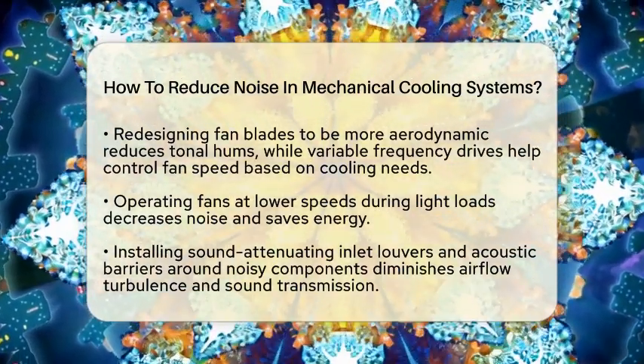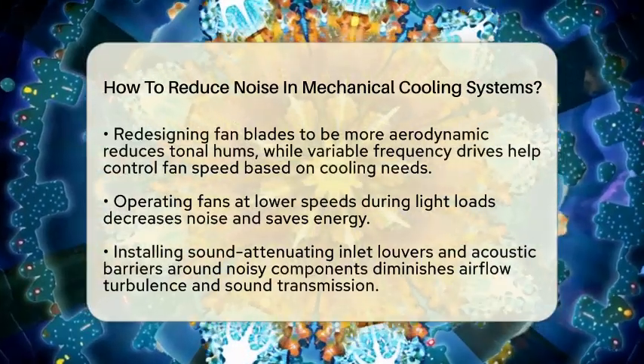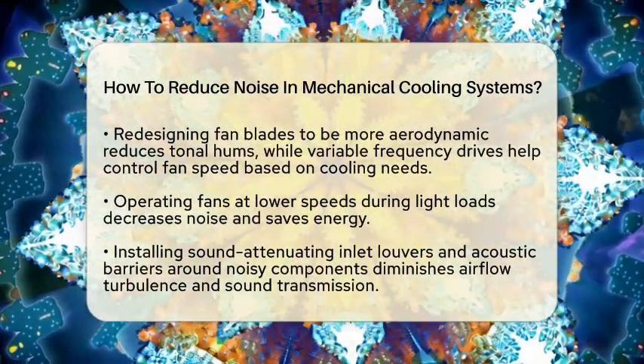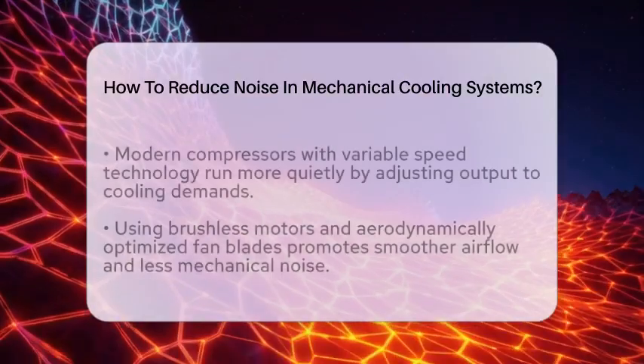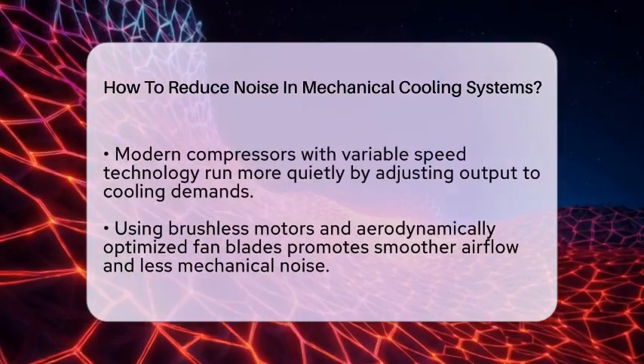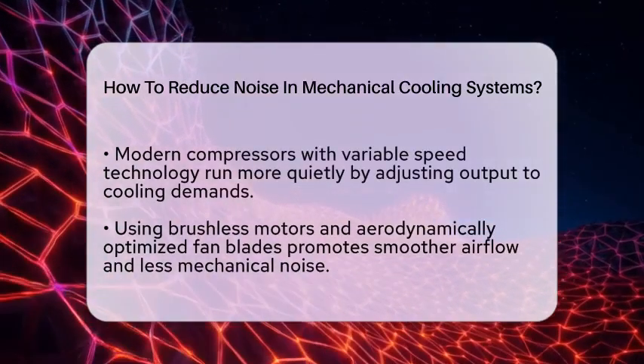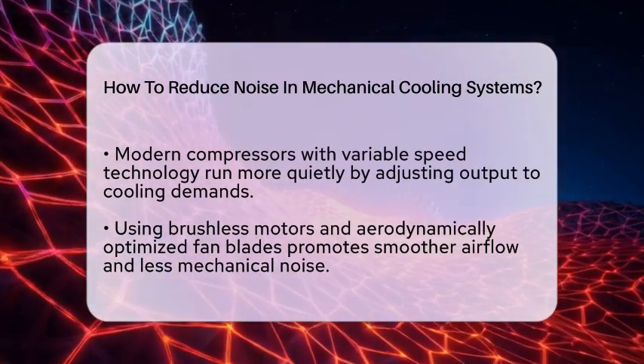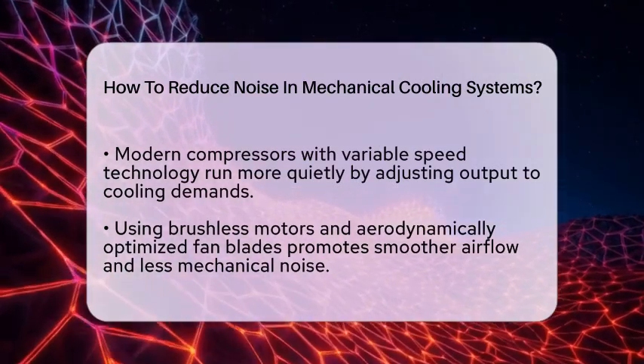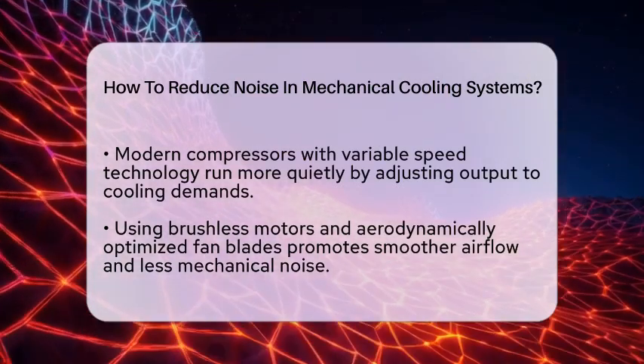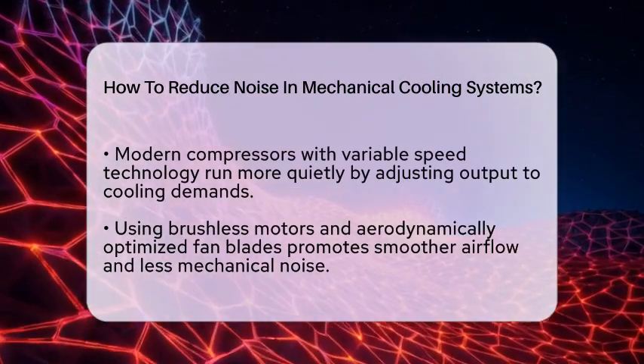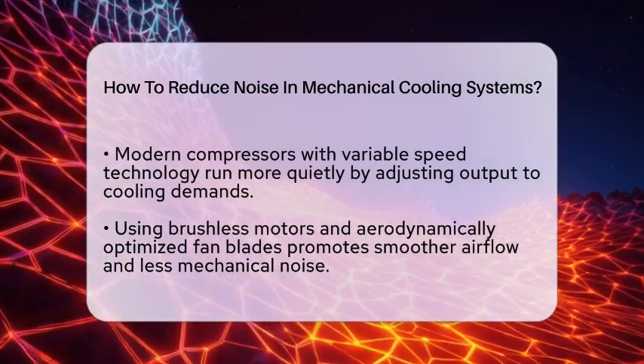Sound attenuating inlet louvers are useful in cooling towers. They help reduce airflow turbulence and water splash noise. Installing acoustic barriers or enclosures around noisy components can also block sound from reaching nearby areas. But it's important to design these barriers so they don't restrict airflow or lower cooling efficiency.